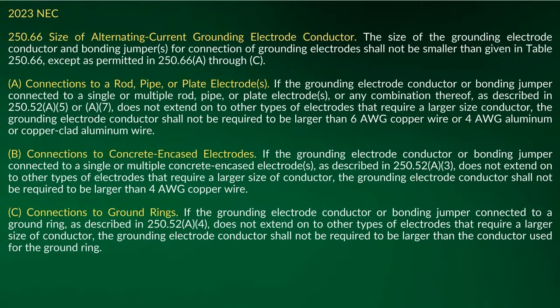Based on substantiations from the code making panel, I'm going to show two, but the main one I'm going to show is a connection to a concrete encased electrode, because somebody submitted a proposal and said they could go smaller. And the code making panel specifically stated that even a number 6 was considered too small for the concrete encased electrode. And that was based on all the testing that was done.